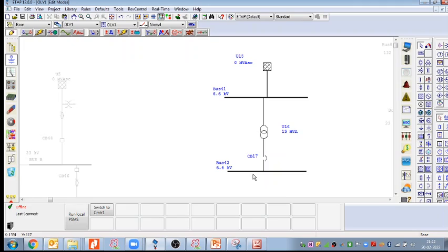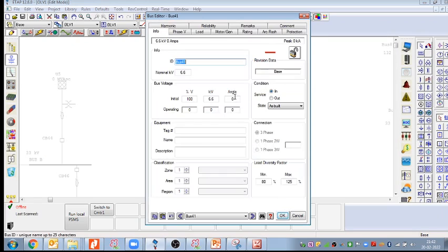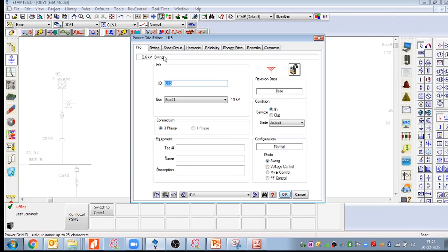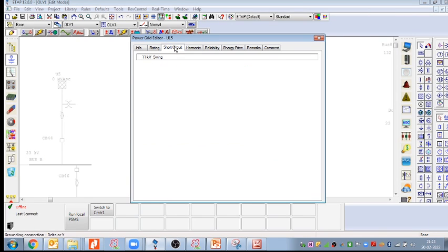Let us take the full fault current that may come, and that fault rating we can take for the entire plant. So suppose this incomer is 11 kilovolt, supporting the 11 kilovolt bus rating, with this 11 kilovolt short circuit rating.